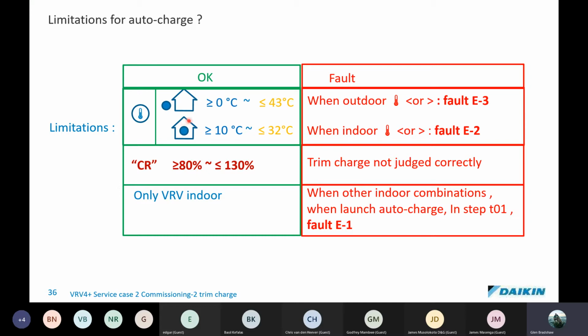The next parameters we need to keep our eye on are the indoor parameters. The temperature must be greater than or equal to 10 degrees Celsius and less than or equal to 32 degrees Celsius. Today in Cape Town it's pretty chilly, probably close to about 12 or so where I am. The other thing that needs to be satisfied, because if you don't get these you'll get an E2 fault: the capacity ratio must be greater than or equal to 80% and less than or equal to 130%, and it must only be done with VRV indoor units.